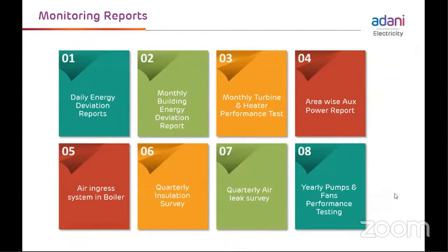Quarterly insulation survey, because this boiler and piping have thermal insulation. We carry out the thermal insulation survey with our infrared cameras to identify deterioration in the thermal insulation. Then we carry out the quarterly air leak survey to identify instrument air leakages in the system and arrest them, thereby reducing the auxiliary power consumption of compressors. Then we carry out pump and fan performance testing on a periodic basis.